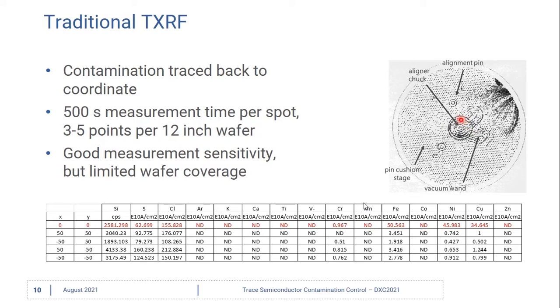the TXRF engineer can report back that the aligner chuck specifically is contaminated with these elements. This was more of a traditional TXRF measurement where we had limited coverage of the wafer — maybe only measuring three to five points on a 12-inch wafer, but we measured for 500 seconds per spot, so we got excellent measurement sensitivity but limited wafer coverage.